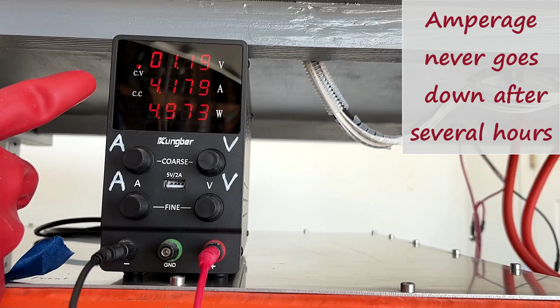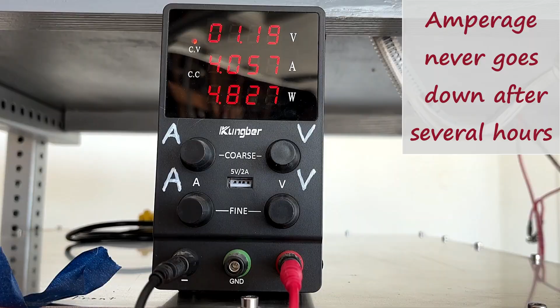I'm going to connect my power supply to module number 1, which we already know is defective. We're sitting at 1 volt, pulling 4 amps. What we're going to find is that it's going to just sit at 4 amps indefinitely. That's how we'll know it's bad. So I'm going to replace this module here, the number 1 module. I have another module I'm going to put in there. The other modules, they are going to come back to life.